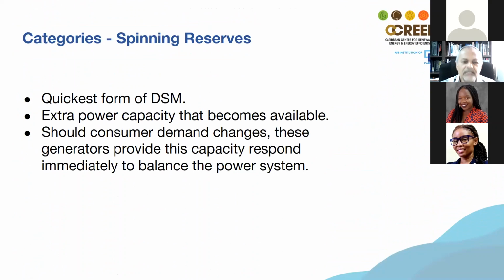Now, the spinning reserve is something I touched on before when we looked at the quickest form of demand side management. Remember, it was at the top of the curve, where in seconds, in terms of cycles, I can really do this because this reserve is already there on the bar. Remember, I talked about a 100 megawatt or a 20 megawatt system where I'm only using 15 megawatts, or 100 megawatts where I'm only using 75 megawatts. I still have 25 megawatts that I can very quickly draw from.